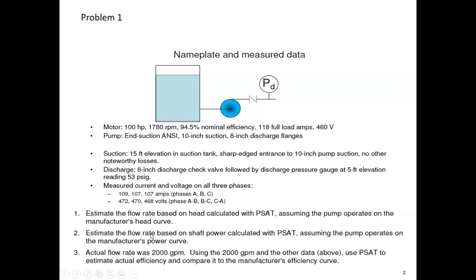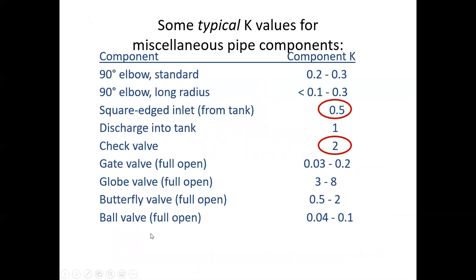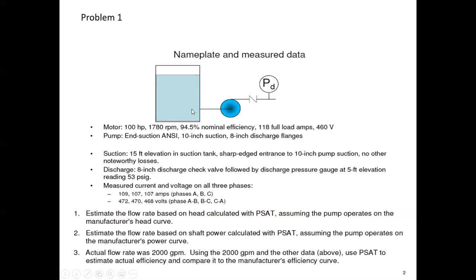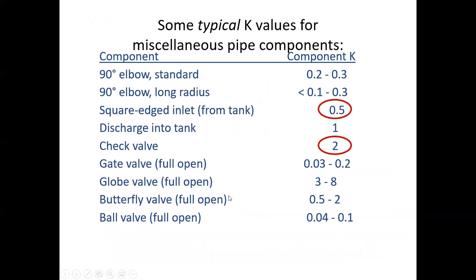And then for the third part, we're told that the actual measured flow was 2000, which may turn out to be different than what we get in 1 and 2. So using the 2000 GPM and the other data above, use PSAT to estimate the actual efficiency and compare it to the manufacturer's efficiency curve. Okay, so that's a fair amount of stuff to do. We have a couple fittings here, right? We have a sharp-edged entrance over here, and we have a check valve over here. I think that's just cut and pasted out of the pump presentation. But anyway, I've circled a couple of them.